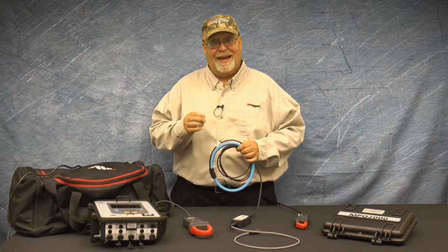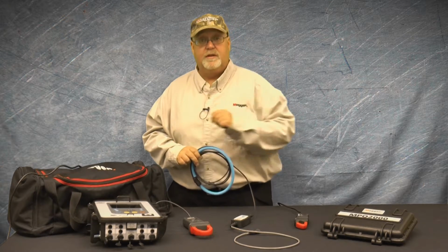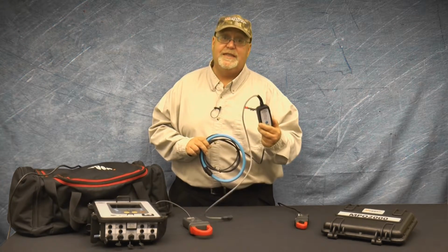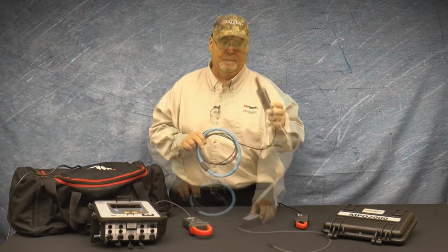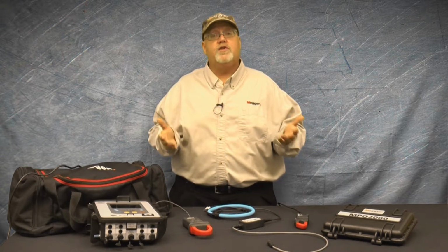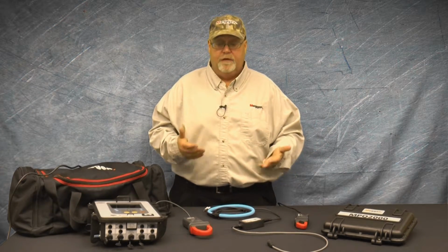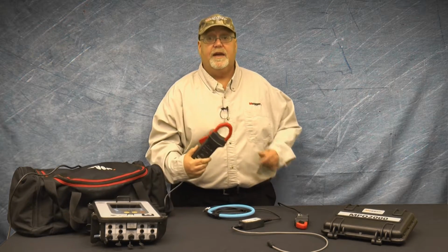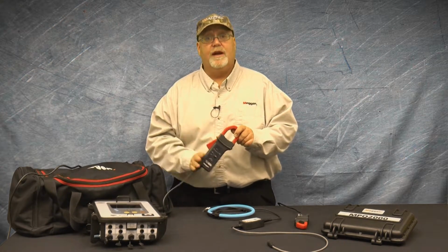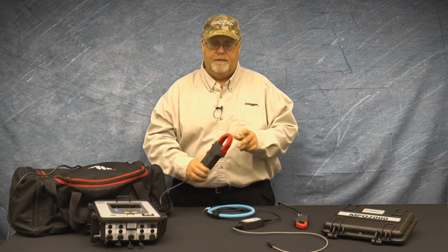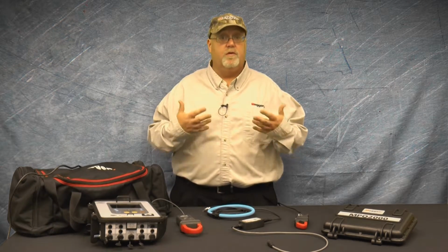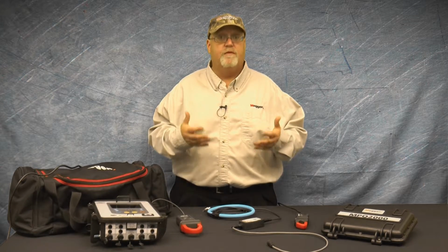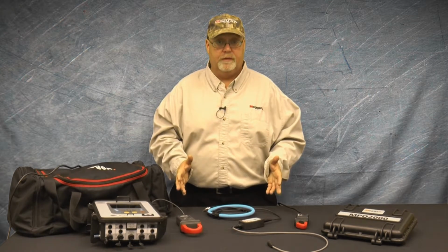If your application's outdoor, not only does the unit need to be weatherproof, but the CT has to be weatherproof as well. Step 3, are you measuring AC or DC? If you're measuring DC, you need to use a Hall effect sensor. And in that case, you have to ask yourself, do I have fresh batteries in it? If your CT requires batteries, you always want to make sure they have fresh batteries before you start the recording.